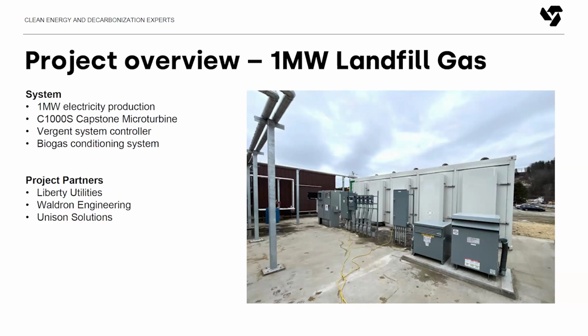There is an H2S vessel just for the compressors, and then the actual gas compression itself to feed the microturbine. The other two project partners we worked with on this project were Liberty Utilities, the local utility. We did have to do a fairly intense impact study due to the fact that there were multiple utilities owning a single substation in the area, and they had a very specific interconnection requirement around being able to trip the systems offline in the event that they need to do work on the lines. But they were a great partner to work with.